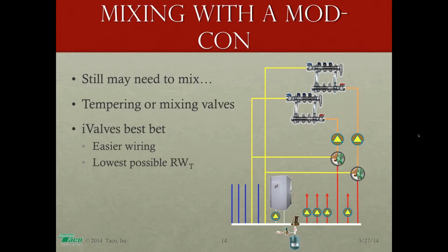Frank Taverna, how you doing, Frank? Glad you're here. I have some contractors who use the reset control of the boiler to set system temperature on radiant systems. If I have a multi-zone radiant system with only one zone operating, will I overheat the radiant panel? That's a great question, Frank, and there's no short answer. The shortest answer is it depends.